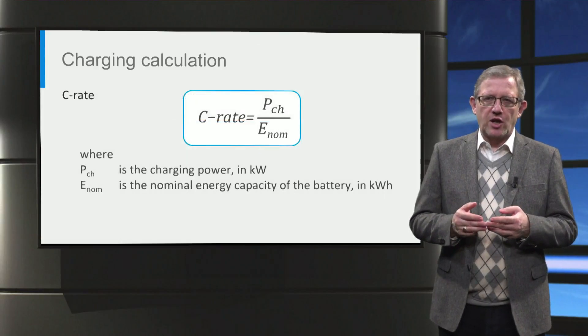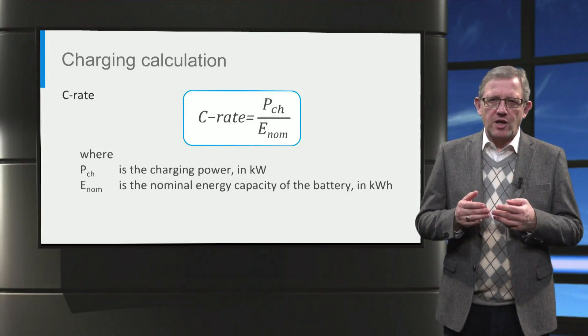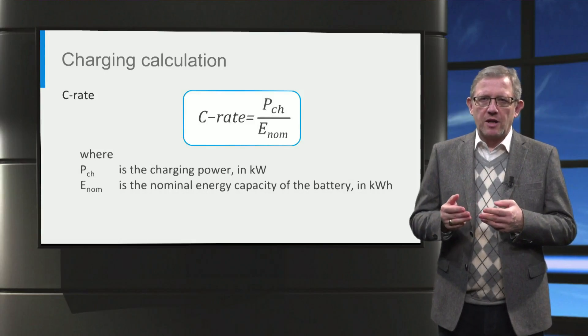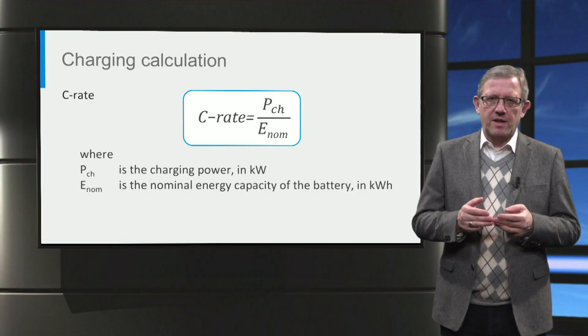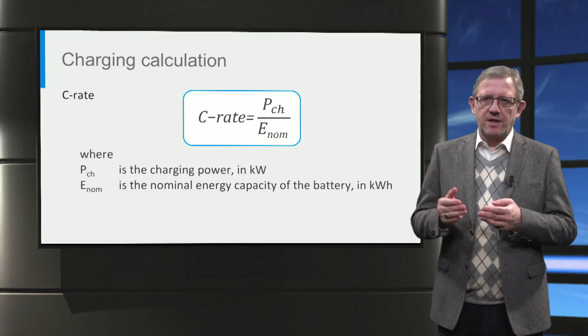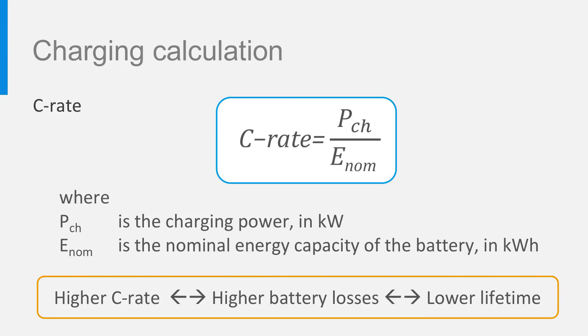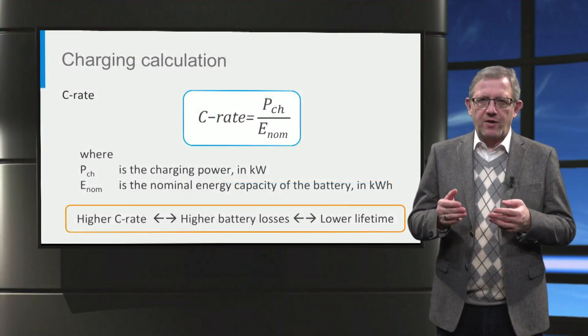The next important parameter is the charge rate, often referred to as C-rate. It is the ratio of the charging power to the nominal energy capacity of the battery. As the charging current increases, so does the C-rate. The importance of C-rate is that as the C-rate increases, battery losses and temperature of the battery increase as well. This eventually reduces the lifetime of the battery. Hence, to ensure the long lifetime of the battery, lower C-rates are preferred.